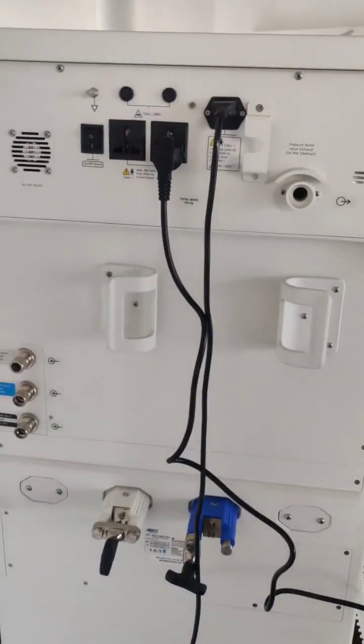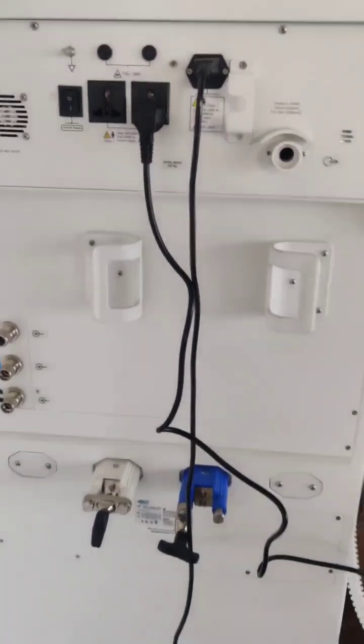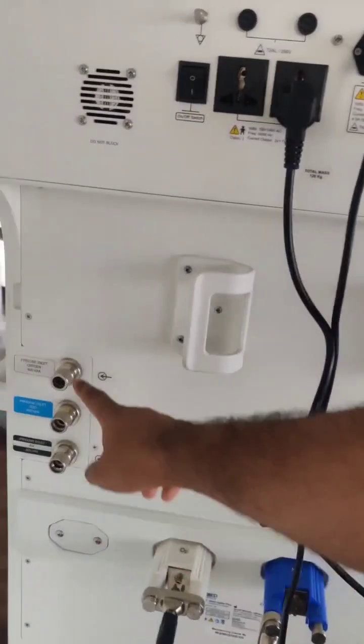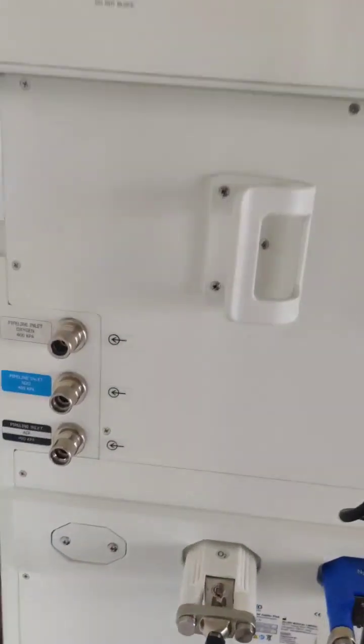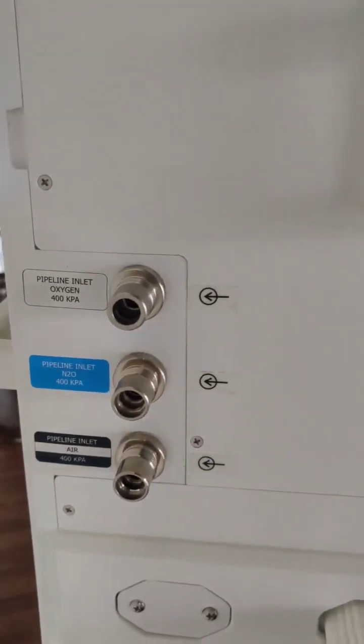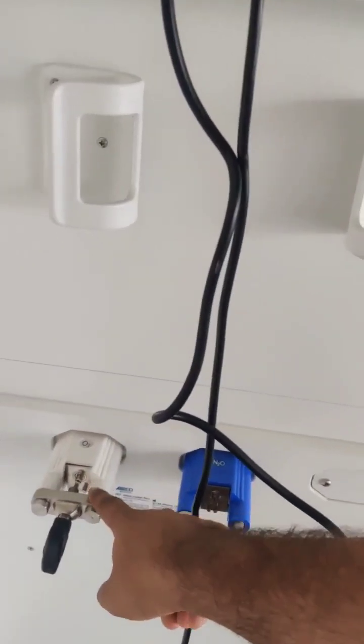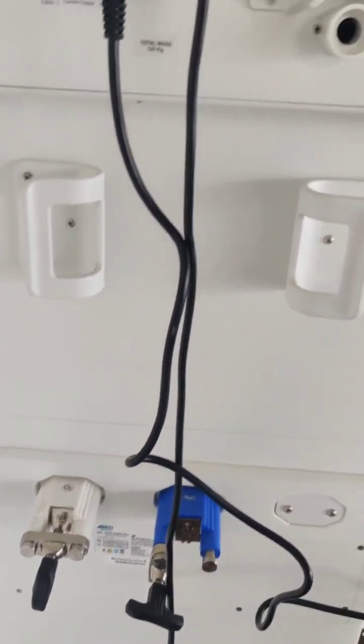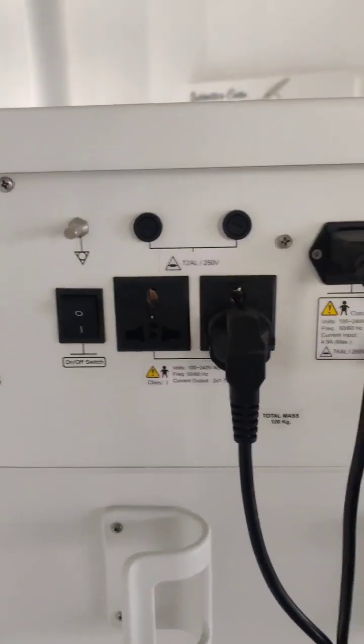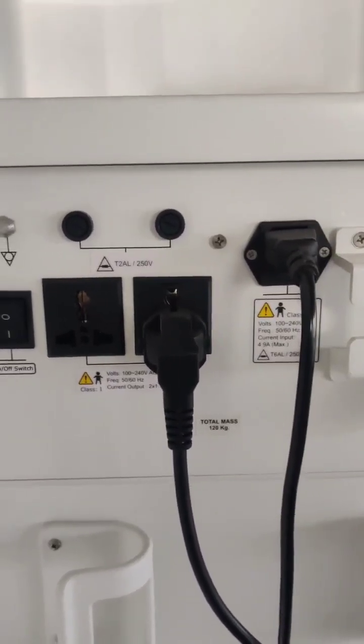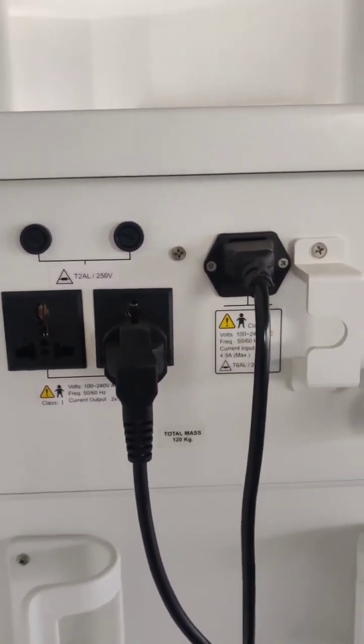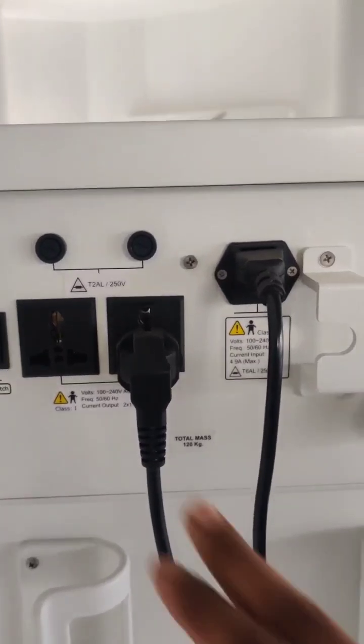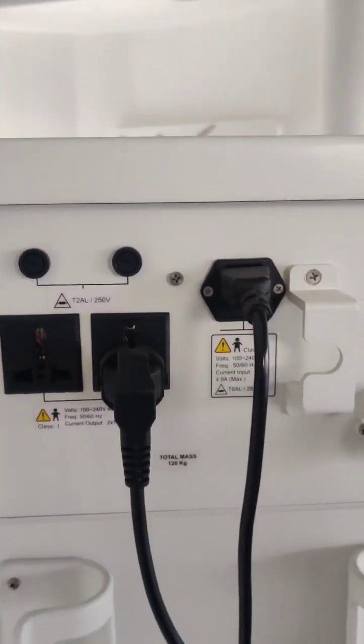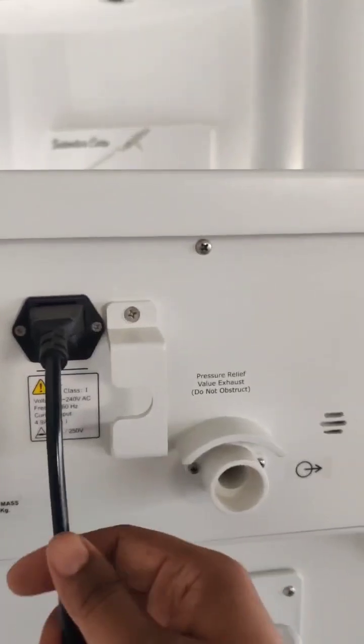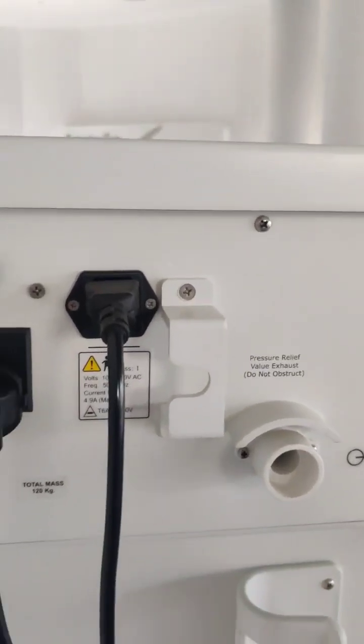Coming to the rear side of the machine, as I mentioned, we have separate pipeline connectors for oxygen, nitrous oxide and air, and one yoke for oxygen and one for nitrous oxide. At the back side we are also giving 2 auxiliary outlets for connecting devices like a monitor. We have a dedicated on-off switch for that, and these are the power sockets. This is for connecting the mains power cord to the machine.